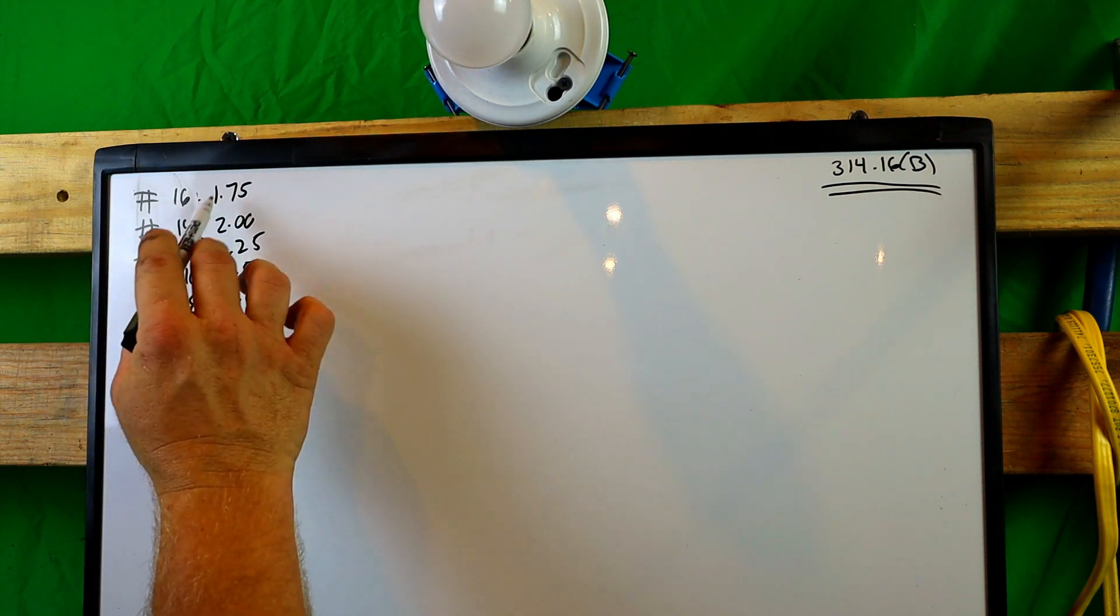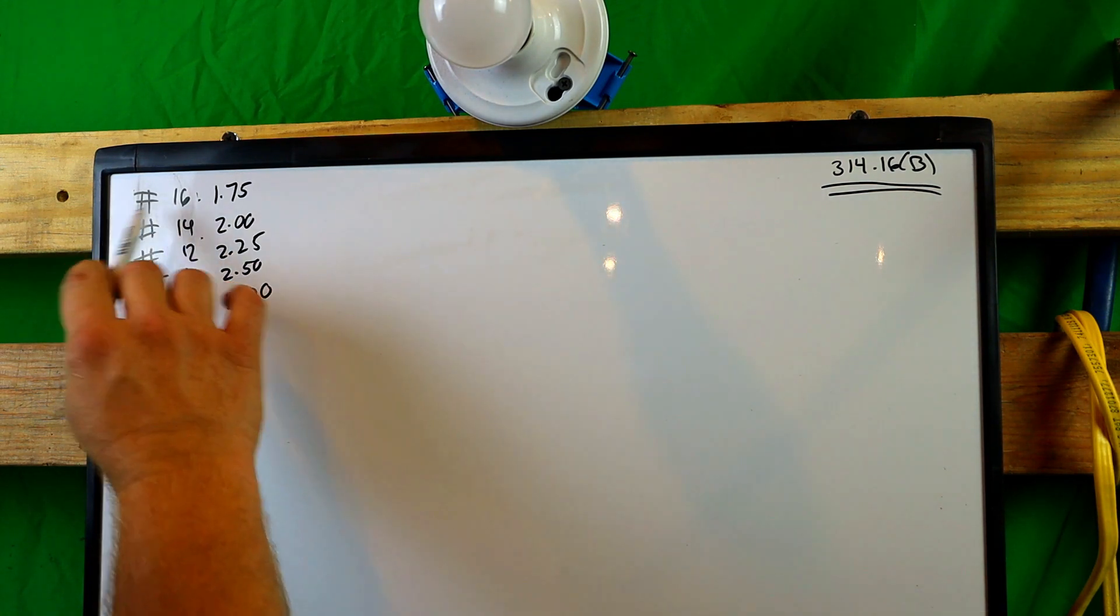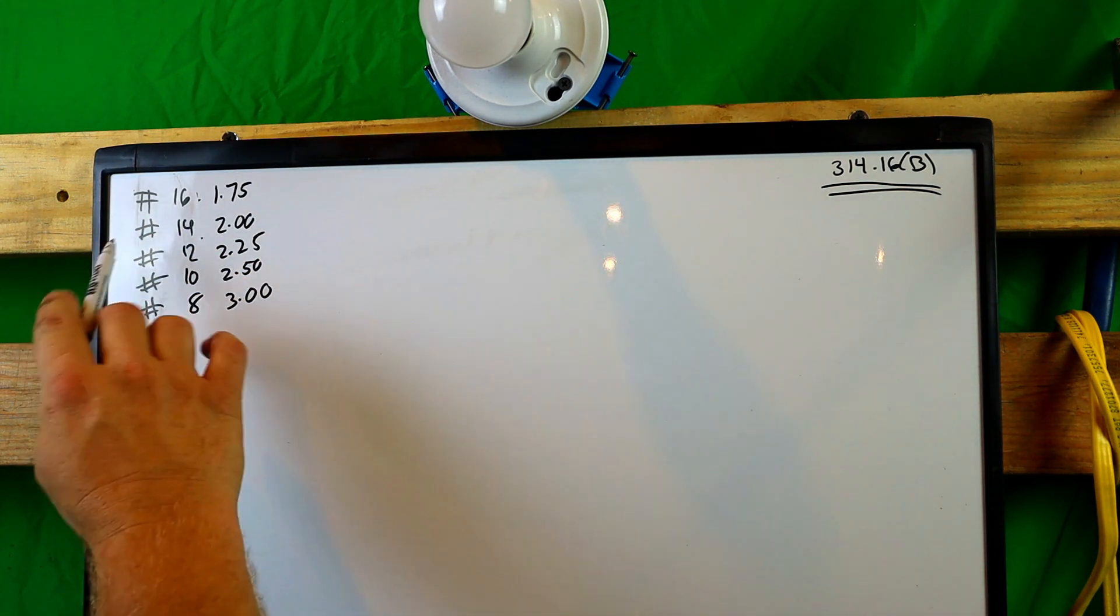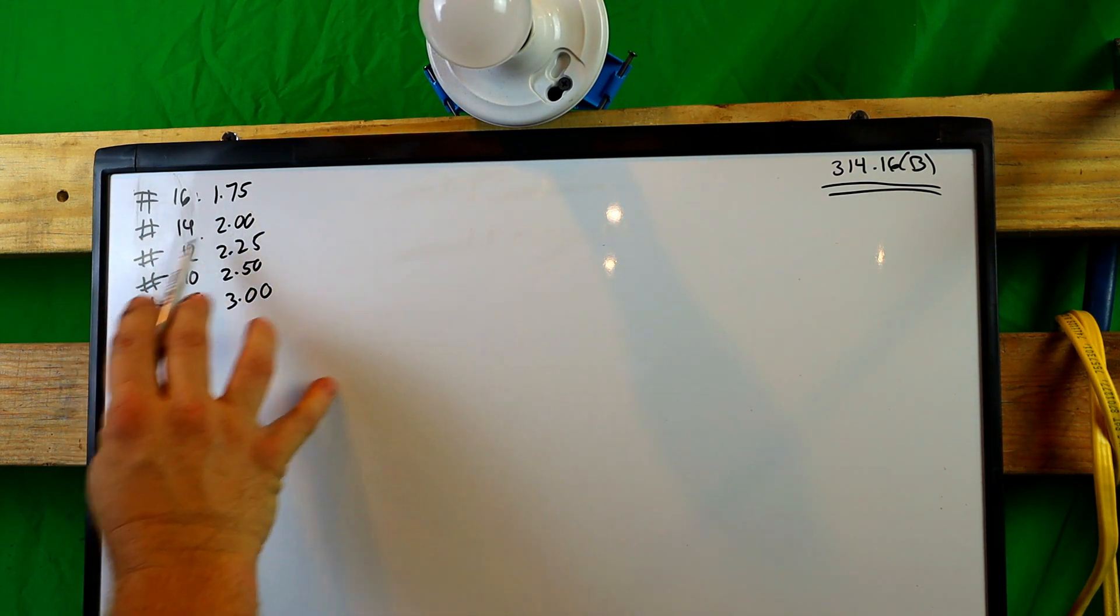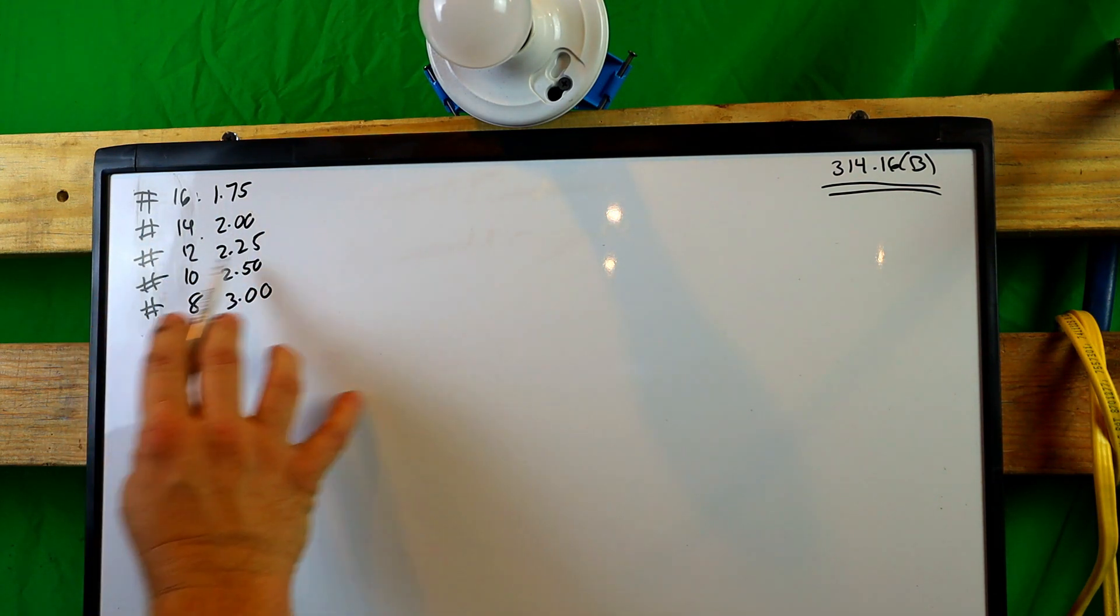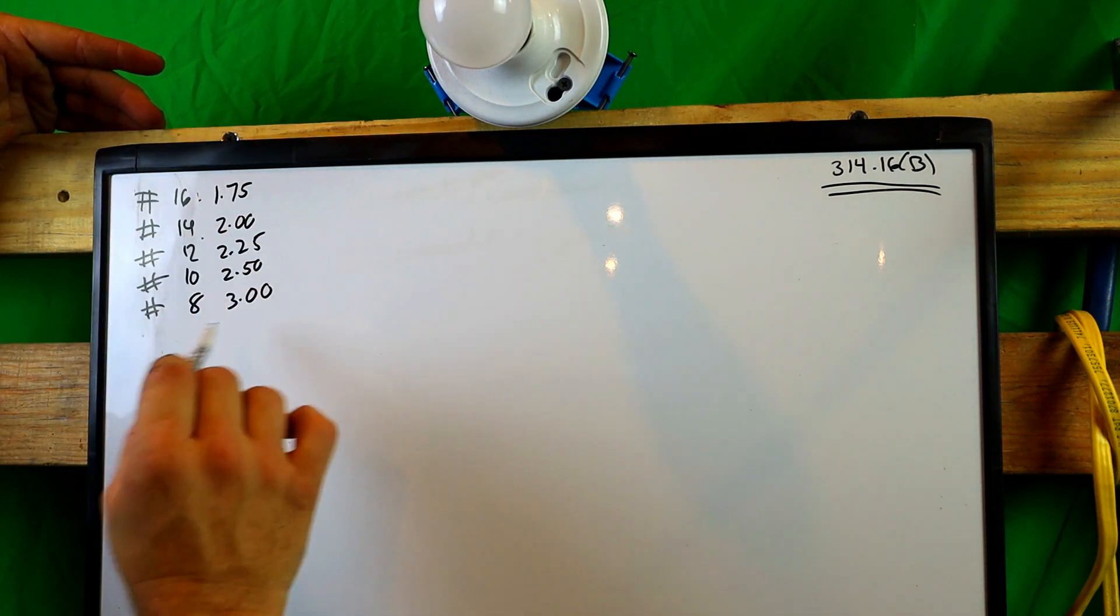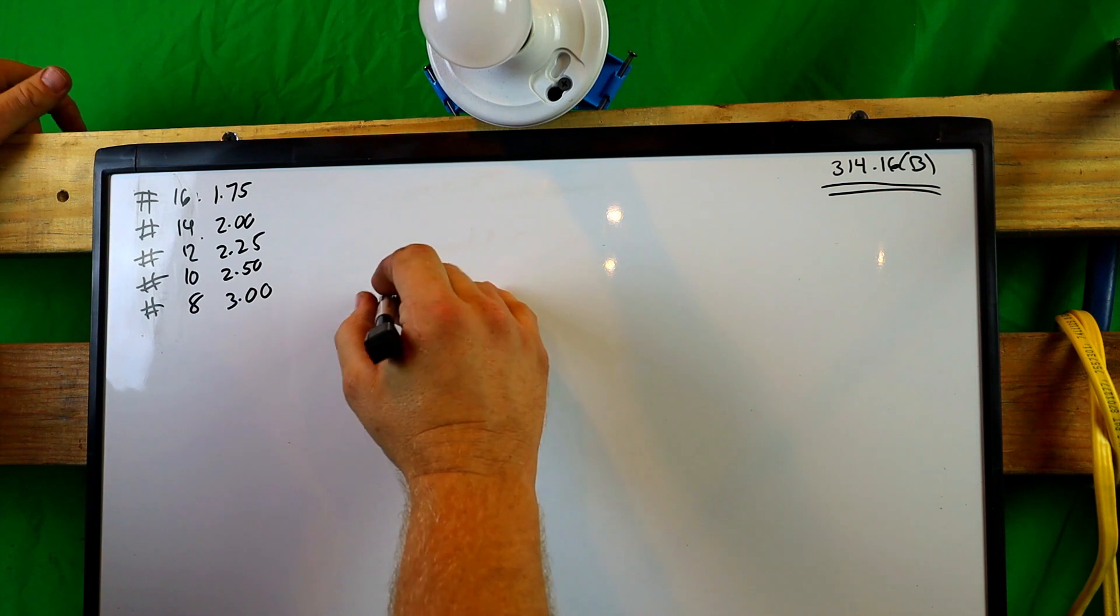Alright. So first things first, every wire has a size rating on it. Now this will all come into play eventually, but they've already had the size right here. So a 16 gauge wire is 1.75, 14 is 2, 12 is 2.25, 10 is 2.50, and 8 is 3.0. You got to know if your box, can you put all those wires in it?